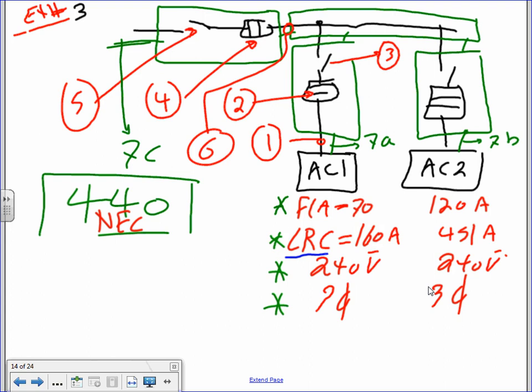Chiller number one or AC number one has the following nameplate information: full load amps 70, locked rotor amps 160, voltage 230/240, three-phase. Chiller number two or AC number two: full load amps 120, locked rotor amps 451, three-phase system.